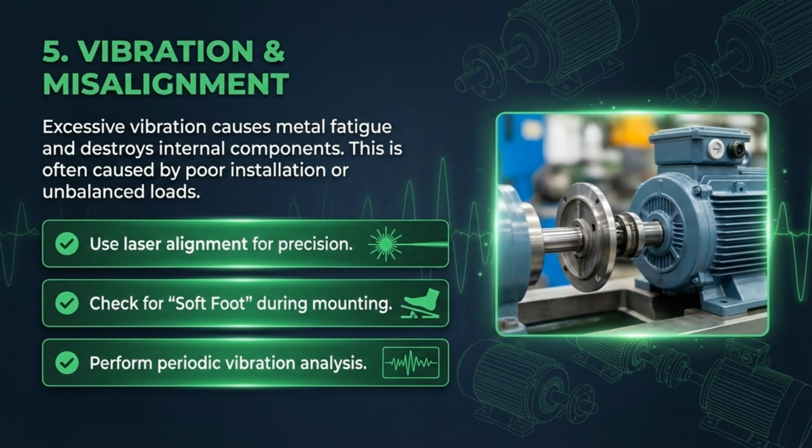Excessive vibration and misalignment cause metal fatigue. Use laser alignment for precision, check for soft foot during mounting, and perform periodic vibration analysis.